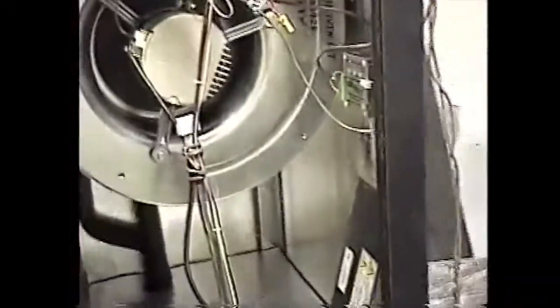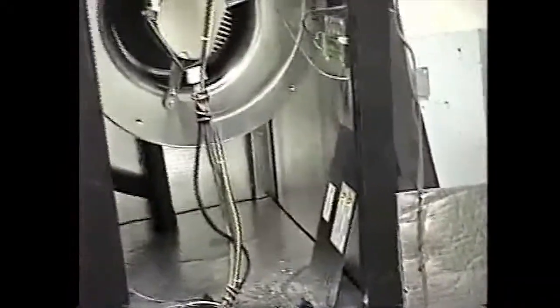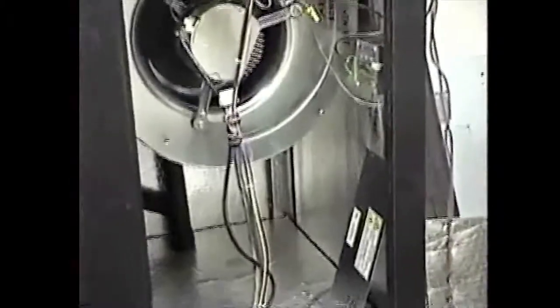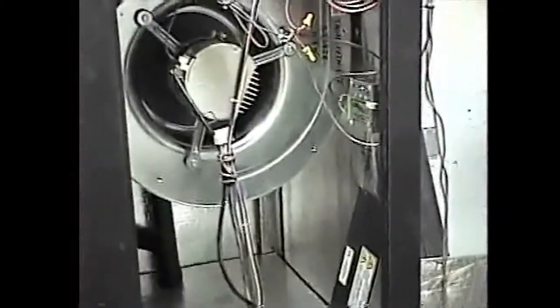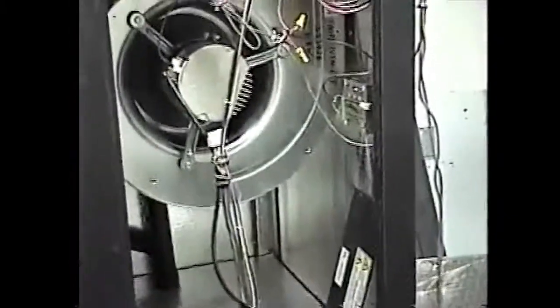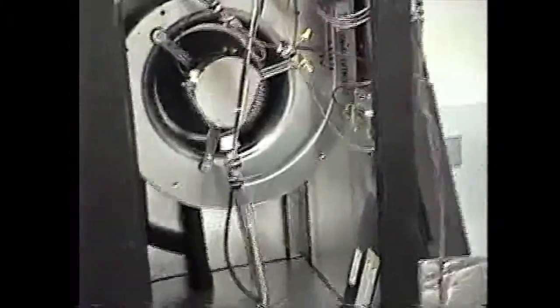Now, you sample all the way around the pipe or all the way around the duct, and make sure that you don't have a place where there's no airflow and there's no accurate sensing of the heat that this thing's putting out. The cooling will take care of itself.